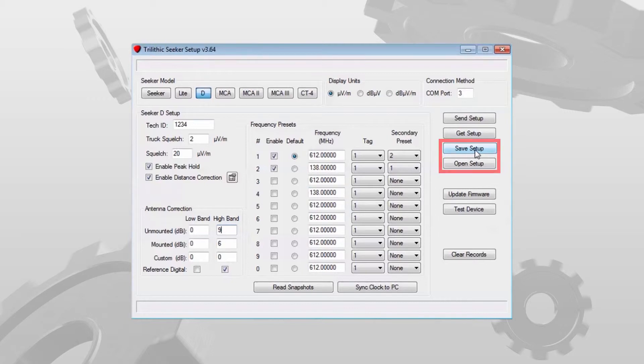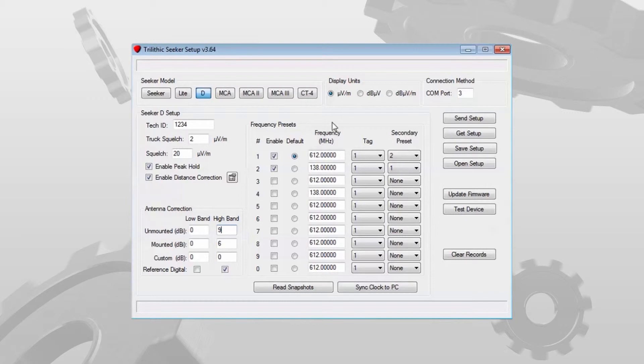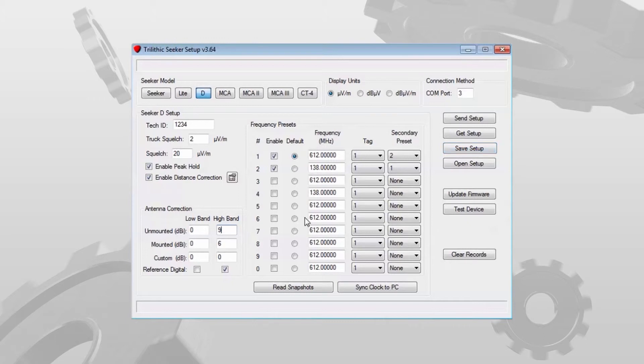I have save setup and open setup. Let's say I've got several units to program and I do half today and I'm going to do half tomorrow. If I've got this already configured with the values that I want, I can save this setup to a file, just save it on my desktop or wherever. And it will save all these settings with the exception of the tech ID because that's unique to each seeker.